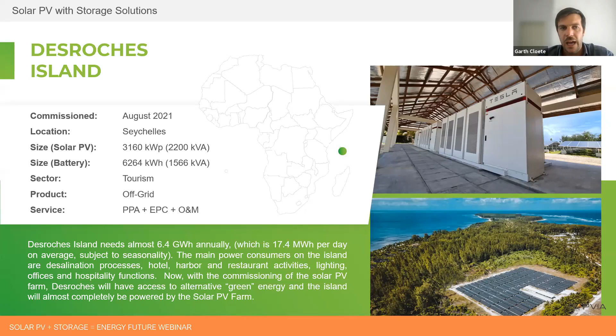One option of addressing that is a typical solar PV diesel hybrid configuration, where you have solar PV feeding in parallel with your existing diesel genset fleet. The diesel remains your grid-forming device, and solar comes in similarly to a normal grid application, with diesel acting as a diesel saver or cost saver. The graph on the right shows the typical impact: it's very much subject to irradiation on site and your ongoing load based on gensets and necessary spinning reserves, but you're able to reduce the diesel you'd have otherwise used—instead of the black dotted line from diesel alone, you end up with that purple line.